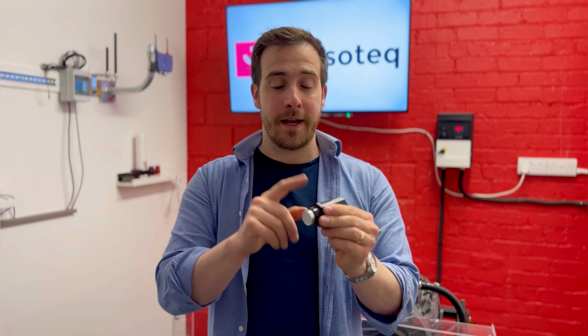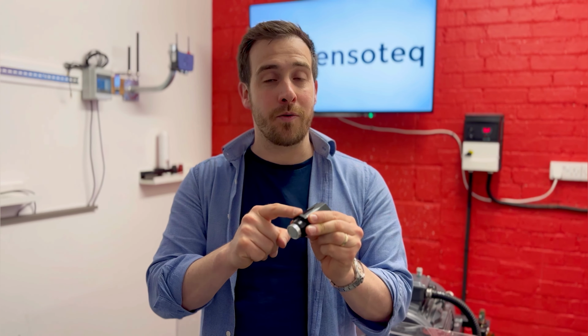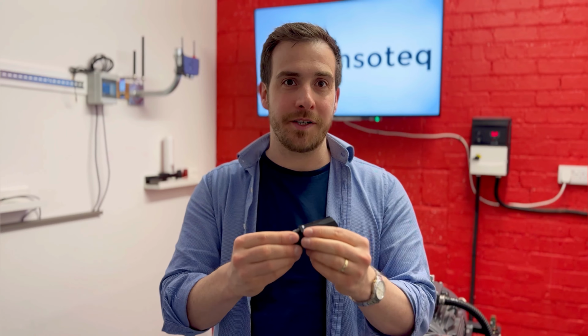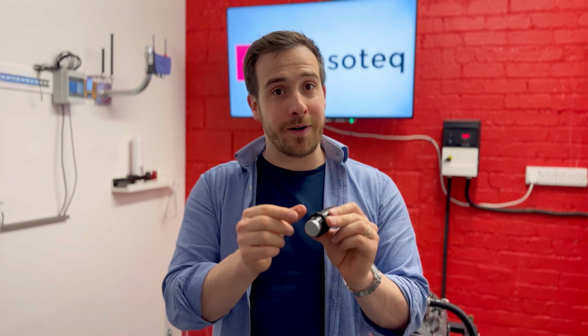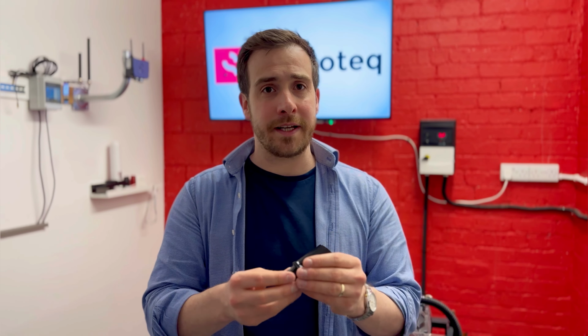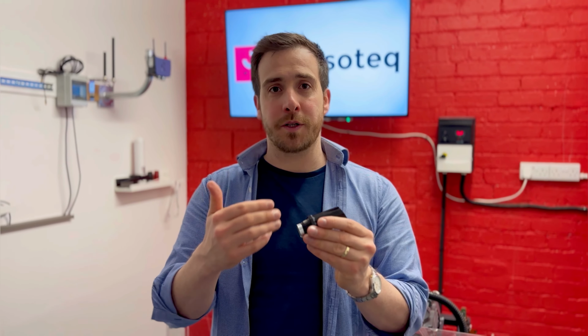Additionally, the path between where the sensor is mounted and where the actual accelerometer or device that reads the vibration signal is mounted is critical. If it's plastic, that could attenuate some of the signal. If it's steel, mild steel, stainless steel, then that's going to give you the best possible response for higher frequency readings. Where the sensor is actually mounted or located on the device is also very important.